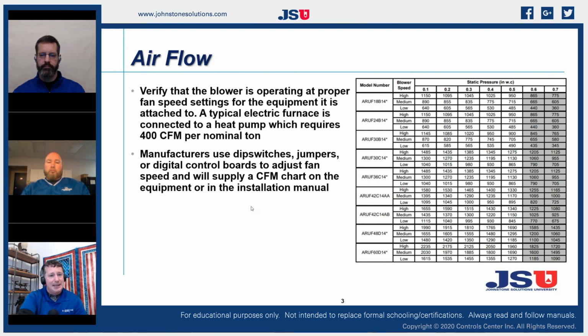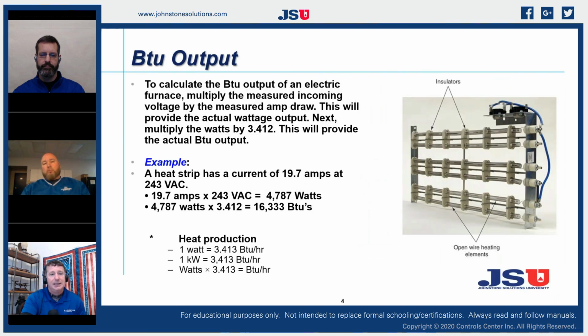So knowing what that static pressure is will truly affect the airflow, right? Because airflow is going to be critical even on our electric furnace to understand the overall operating condition of particularly our electric elements. So if we look at an element, an electric element, it's a very simple construction, right? It's a high resistance wire that is insulated inside of ceramic insulators. So it's basically an open wire, right, that we're going to apply voltage to.